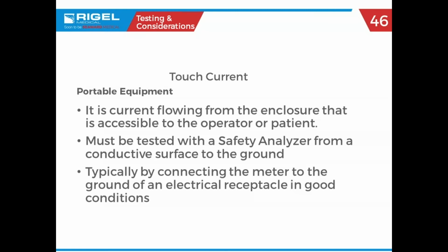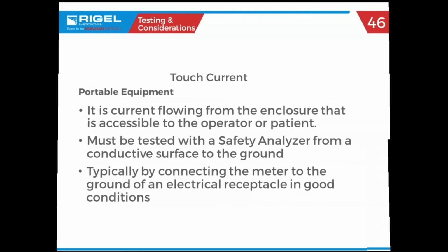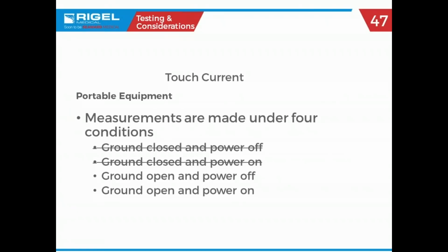So that's that. So here's a big change. Touch current. You used to have to do it in normal operating condition and in a single fault condition. It makes all the sense in the world that if it passes in single fault condition, it would pass in normal operating condition. So NFPA 99 now says for your touch current, you only have to test in single fault condition. So the ground open is our only single fault condition in NFPA 99.